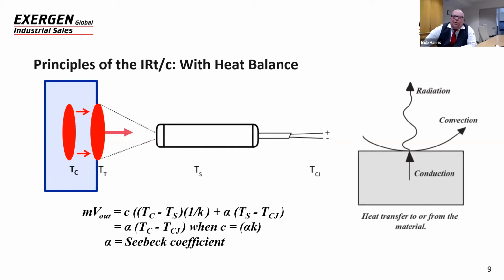So what we could do is calibrate this sensor, because it all correlates. When the core temperature changes, the surface temperature changes. So we can calibrate that sensor so that it actually displays the core temperature rather than the target temperature. And that's one of the things we're going to talk about here and show you some examples later on in the presentation, where customers are actually using this heat balance technique with a specially calibrated IRTC for heat balance.